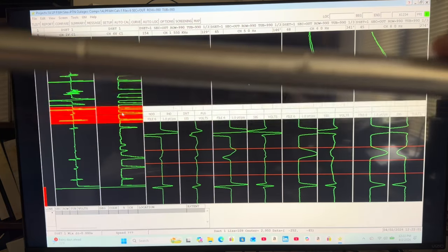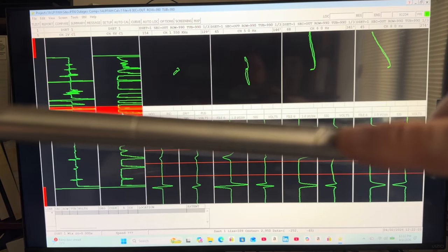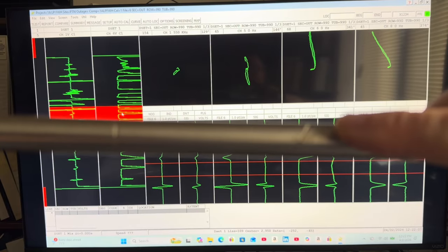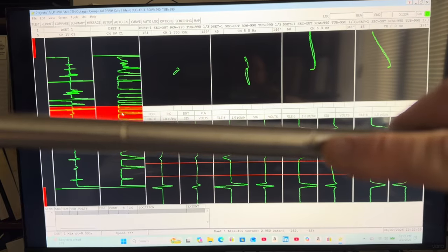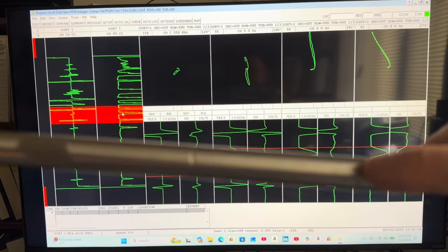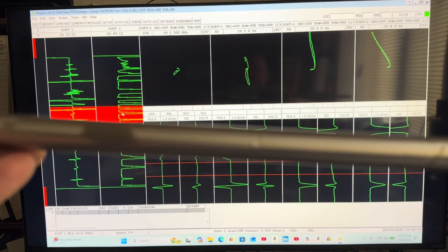There's a hacksaw blade right there, diagonal. So, you don't see too many diagonal flaws in a heat exchanger tube, although you could if you had some foreign object or foreign material in there wearing at your tube OD at an angle.